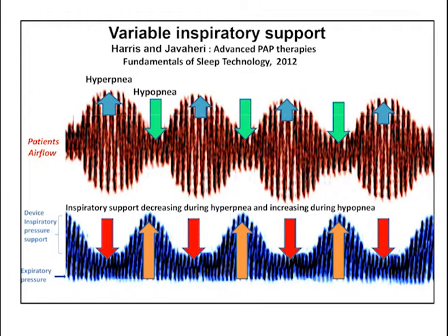With the ASV devices, it's a different ballgame. If the patient has a breathing pattern like Cheyne-Stokes breathing—hyperpneic here, hypopneic here, cycling up and down—the device is anti-cyclic. What do I mean by that? When the patient is breathing excessively, the inspiratory pressure support goes down; when the patient is having hypopnea, the inspiratory pressure support goes up. So it's an anti-cyclic kind of augmenting ventilation—supporting when the patient is hypoventilating, withdrawing support when the patient is hyperventilating. This may be more comfortable in the long run for patients who aren't sleepy to begin with.